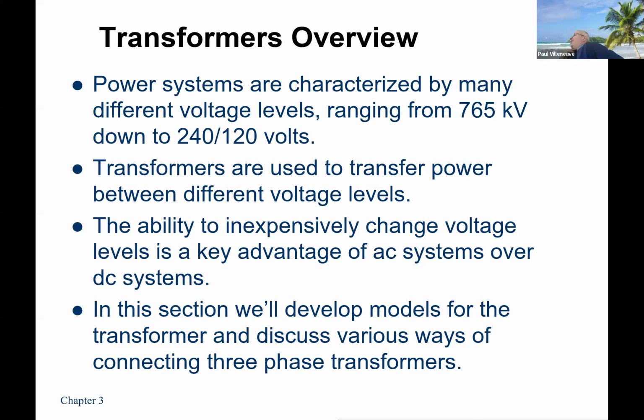Also, I went to Clemson, South Carolina, where Clemson University is, and looked at their electrical distribution system. I think they had 10 MVA transformers, and they had single phase ones. The reason is that if one transformer failed, you could just plug in another one. They had a spare one on campus so that they could maintain the reliability of the system. Because on a college campus there are 10,000, 15,000 people living there. It's pretty darn important to maintain electricity.